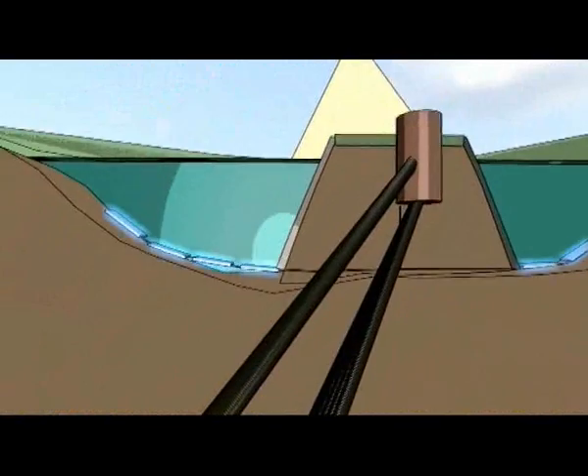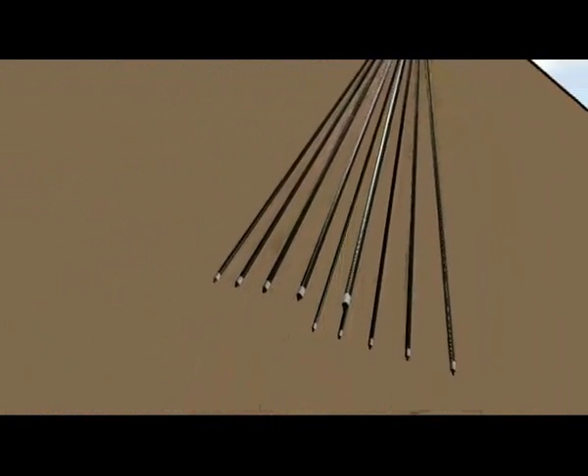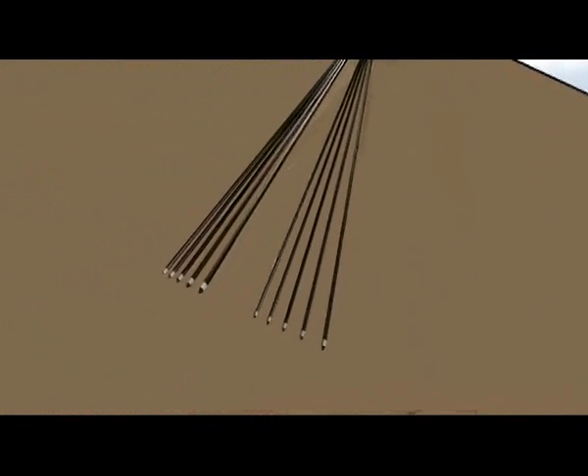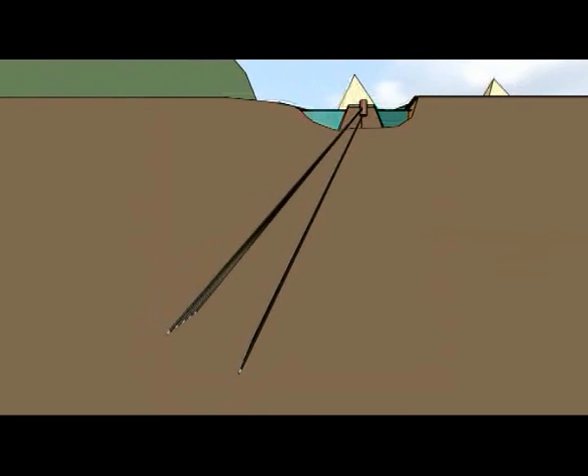The innovative GRD method, GRD stands for Geothermal Radial Drilling, combines the advantages of horizontally installed ground heat collectors and vertically installed ground heat pipes. With a maximum bore depth of 40 meters, groundwater-bearing strata are hardly affected. That's why the method meets the license requirements, even for bores in water protection areas.